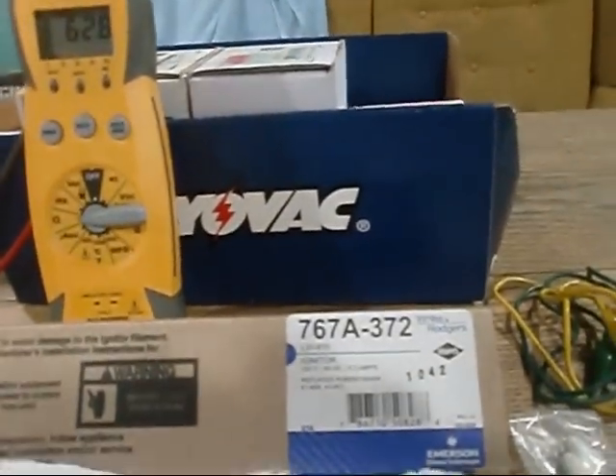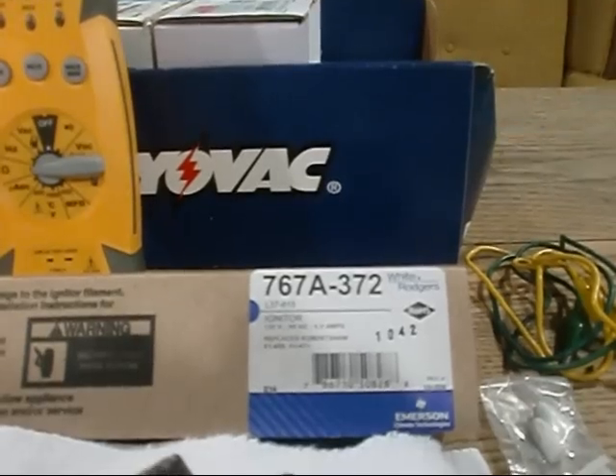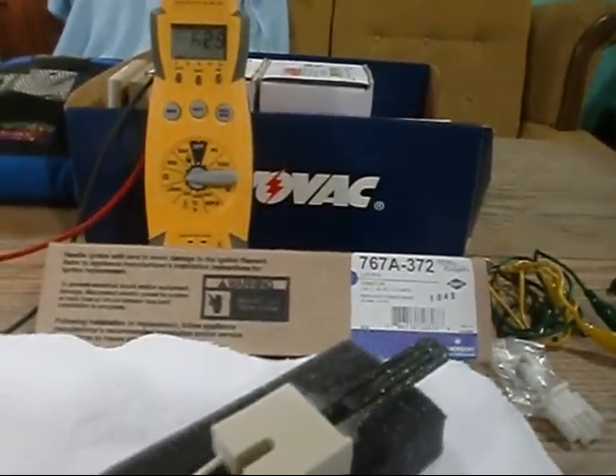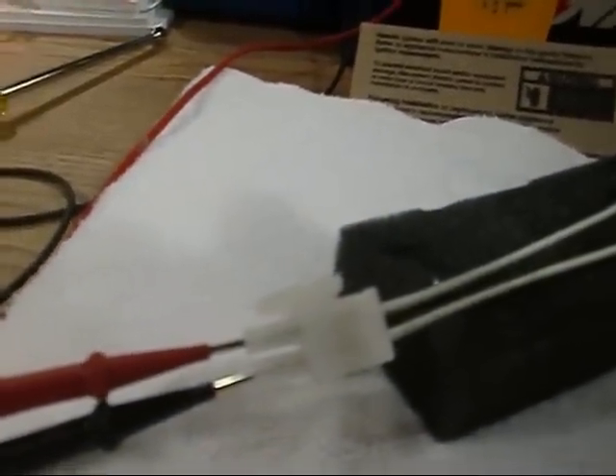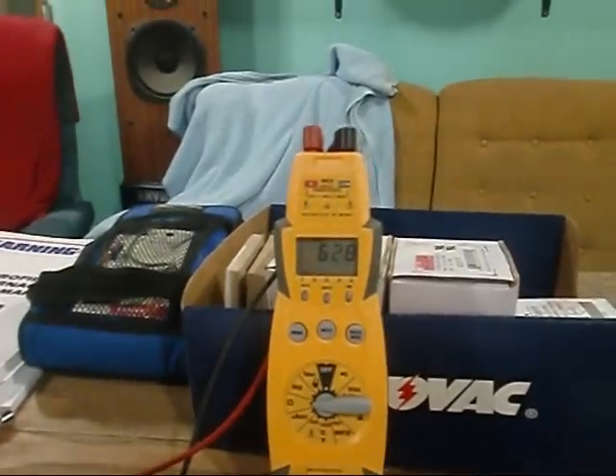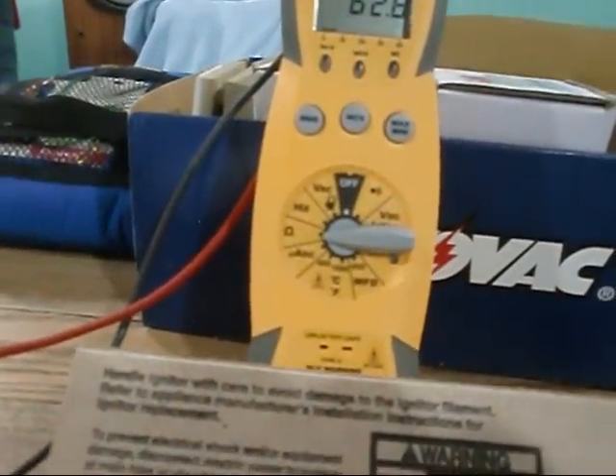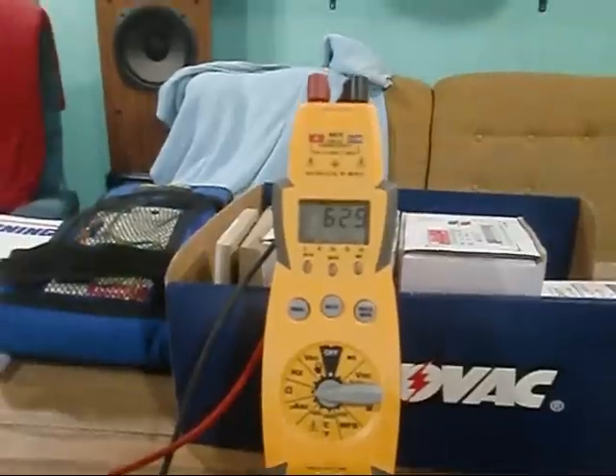We're going to start out with this 767A-372 White-Rodgers igniter, 120 volt, 5 amp. I've got my Fieldpiece fired up with the probe stuck in the bottom. I tried not to jam them in too hard — didn't want to ruin my new igniter. Like I said, I was always told 40 to 90 ohms, and we're looking at 62.8 on this one, set to ohms.